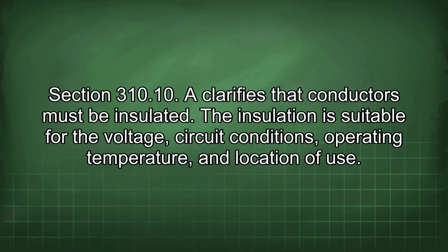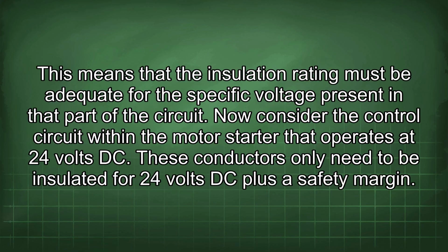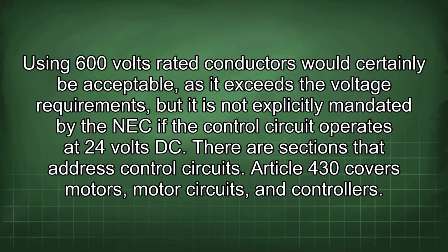Section 310.10 clarifies that conductors must be insulated. The insulation is suitable for the voltage, circuit conditions, operating temperature, and location of use. This means that the insulation rating must be adequate for the specific voltage present in that part of the circuit. Now consider the control circuit within the motor starter that operates at 24 volts DC. These conductors only need to be insulated for 24 volts DC plus a safety margin. Using 600 volt rated conductors would certainly be acceptable, as it exceeds the voltage requirements, but it is not explicitly mandated by the NEC if the control circuit operates at 24 volts DC.